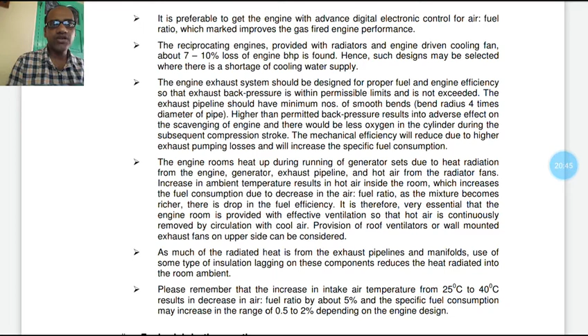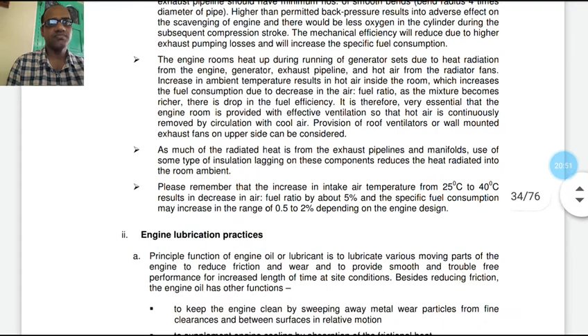To reduce radiated heat from the exhaust pipeline and manifolds, use of some type of insulation lagging on these components reduces the heat radiated into the room ambient. And please remember that the increase in intake air temperature from 25 degrees centigrade to 40 degrees centigrade results in a decrease in air fuel ratio by about 5%. And specific fuel consumption may increase in the range of 0.5 to 2% depending on engine design.